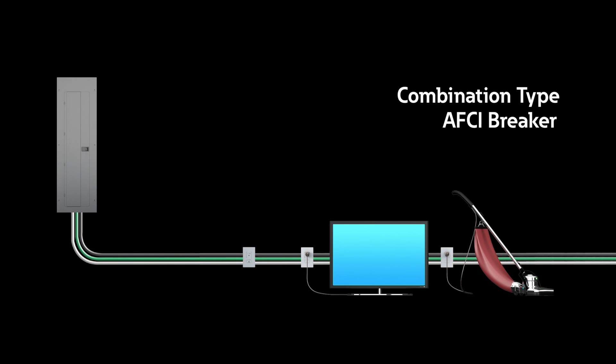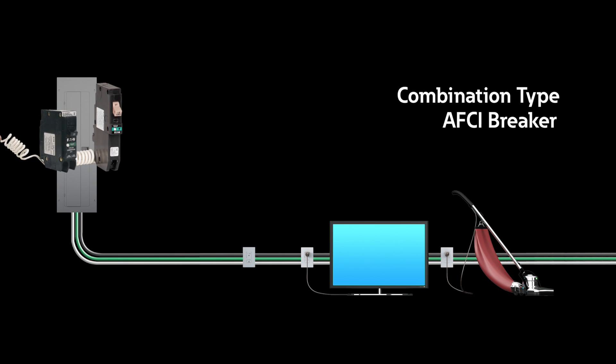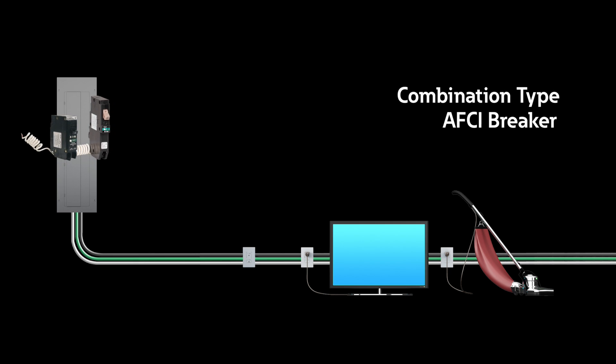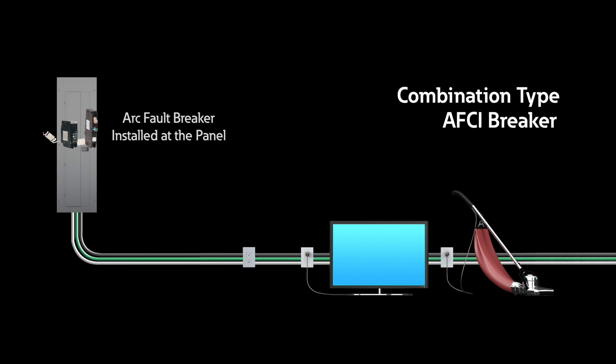Combination type AFCI breaker. This is the most common and most complete way to provide AFCI protection. It is installed at the panel and safely detects both parallel and series arcs in the entire branch circuit, including the home run circuit and downstream out through the connected cords.